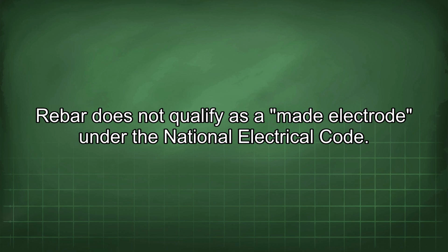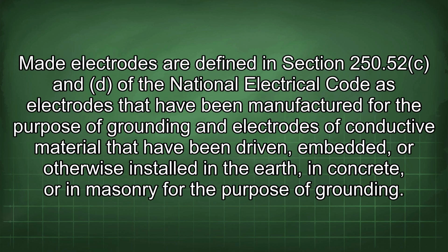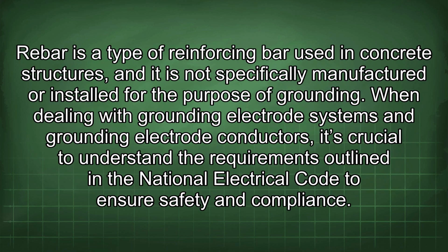Rebar does not qualify as a made electrode under the National Electrical Code. Made electrodes are defined in section 250.52 C and D of the National Electrical Code as electrodes that have been manufactured for the purpose of grounding and electrodes of conductive material that have been driven, embedded, or otherwise installed in the earth, in concrete, or in masonry for the purpose of grounding. Rebar is a type of reinforcing bar used in concrete structures, and it is not specifically manufactured or installed for the purpose of grounding.